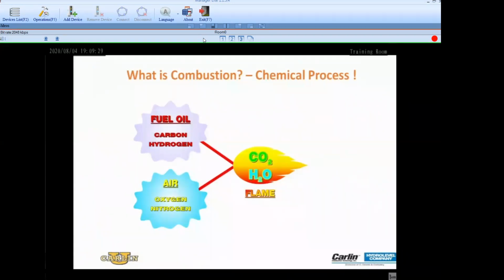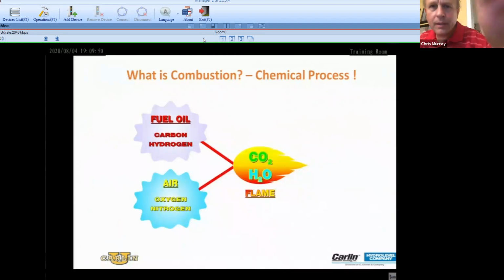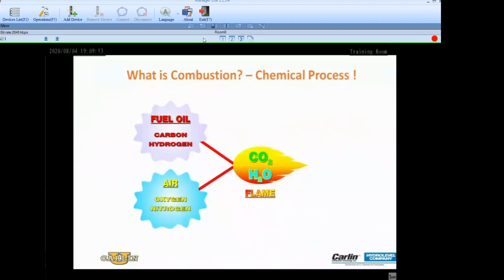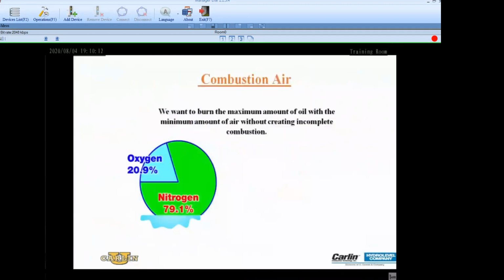Carbon and hydrogen, oxygen and nitrogen. You combine them to get CO2 and H2O. There is a flame present that you're seeing, but this conversation is about combustion being a chemical process. If we can get people away from thinking of combustion as a flame that has a color or a pattern, something you can see by sight and adjust to a particular color or pattern, then technicians would understand that you can't adjust by sight. You have to have instruments. BTUs are the end result. That's what we're after, the heat produced.